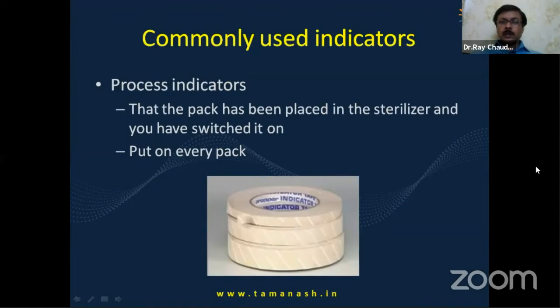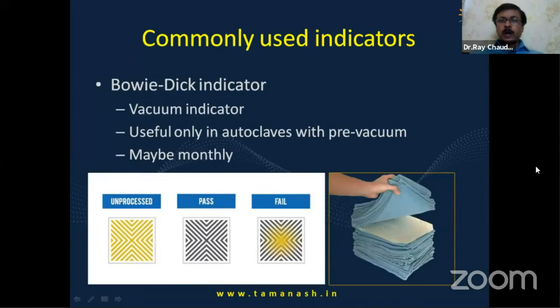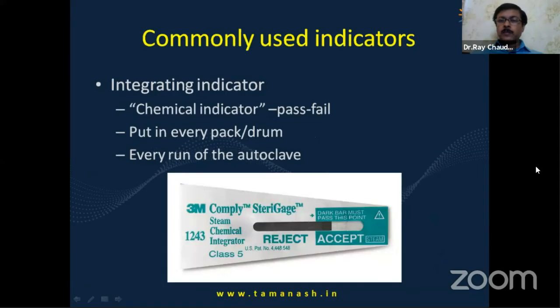So what are these? Class 1 indicators are process indicators, which means that the pack has been placed in the sterilizer and you have switched the sterilizer on. So heat has reached the package. So this is a process indicator and it must be used in every pack. Bowie-Dick indicator is a class 2 indicator, which is a vacuum indicator and useful in autoclaves with pre-vacuum, and it only shows that the pre-vacuum part is working properly, and there is a challenge test in which you have to place it within a set of towels and look at the result. So this must be done about once a month, or if you suspect the autoclave is malfunctioning.